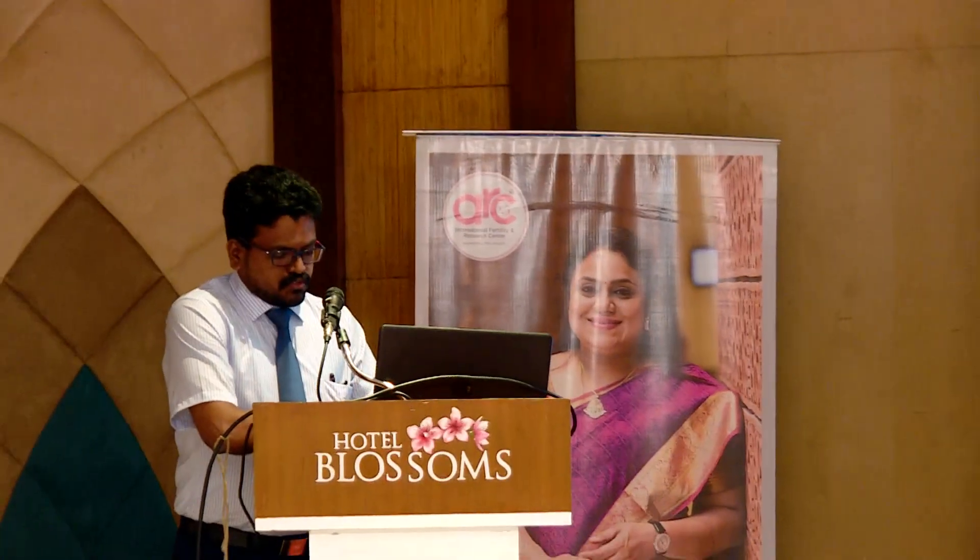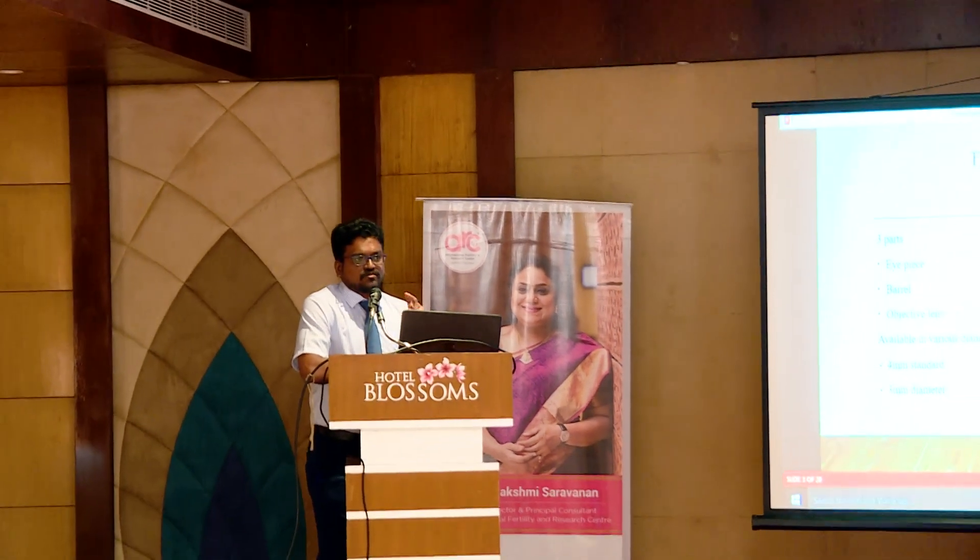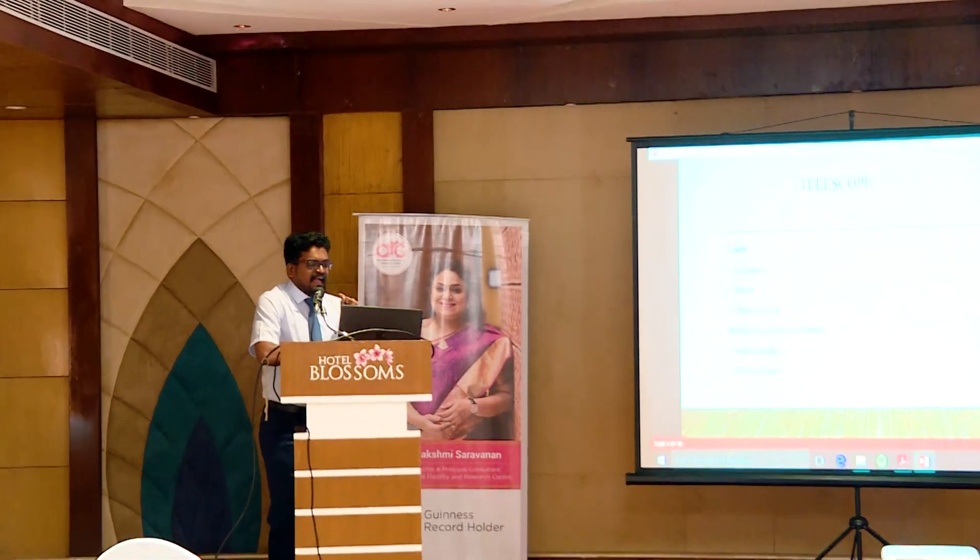Coming to the telescope, there are three parts: the eyepiece, the barrel, and the objective lens. Various diameters exist — 4 mm, 3 mm, and 2.9 mm. Commonly we use the 2.9 and 4 mm diameter. The 2.9 mm is used for office hysteroscopy and the 4 mm for interventional hysteroscopy. We should definitely have both — 2.9 and 4 mm.